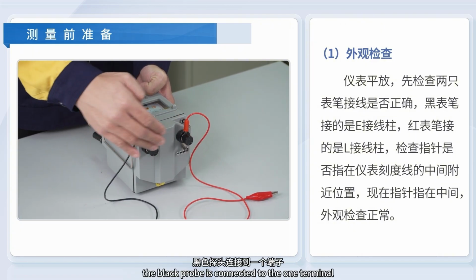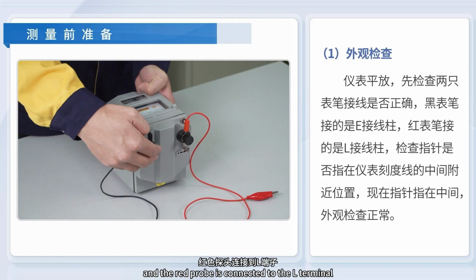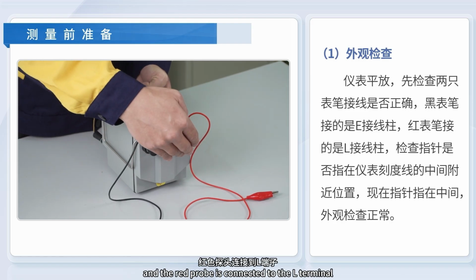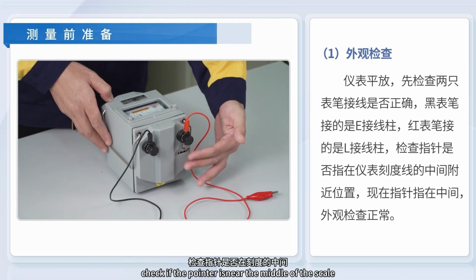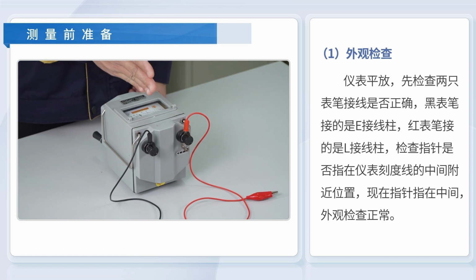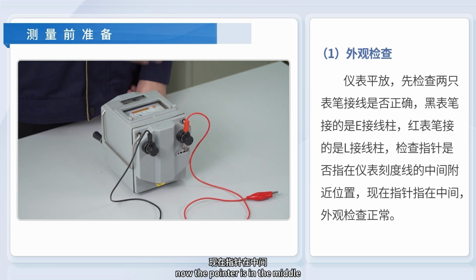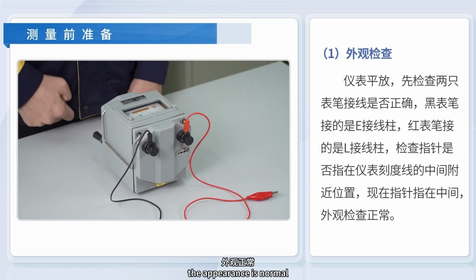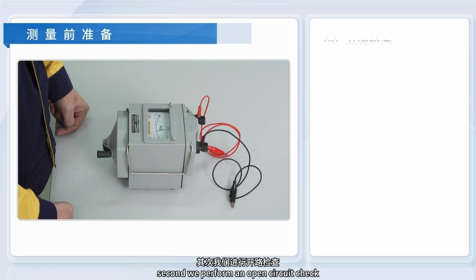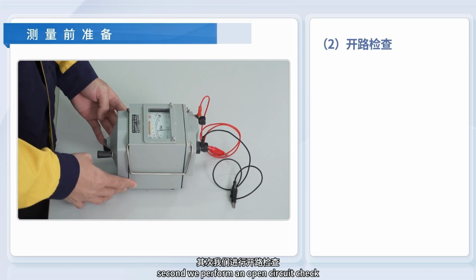The black probe is connected to the E terminal, and the red probe is connected to the L terminal. Check if the pointer is near the middle of the scale. Now the pointer is in the middle. The appearance is normal. Second, we perform an open circuit check.